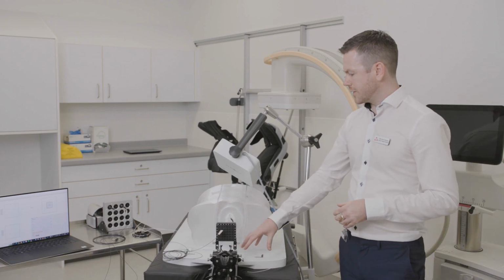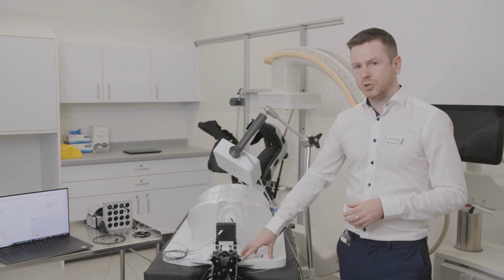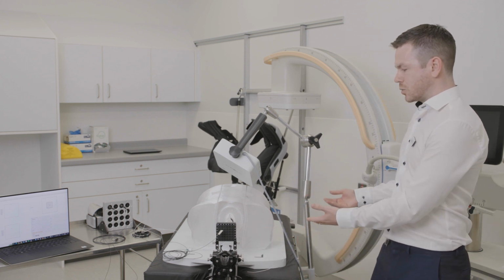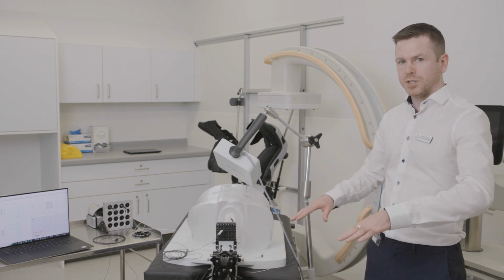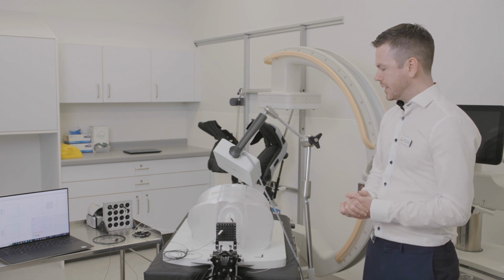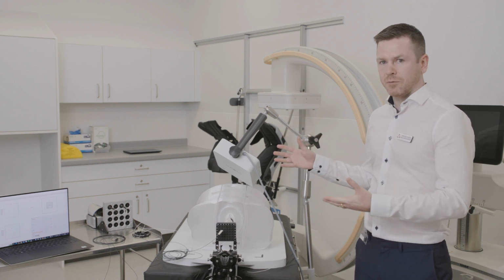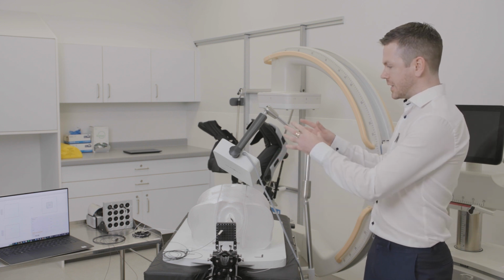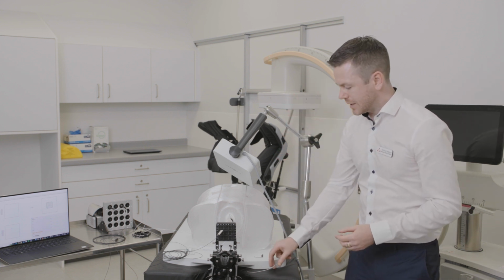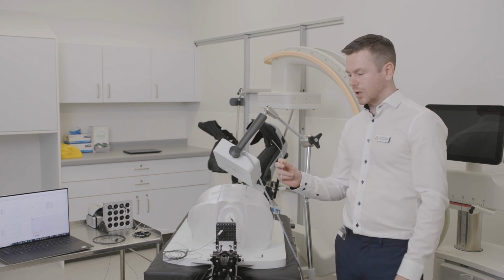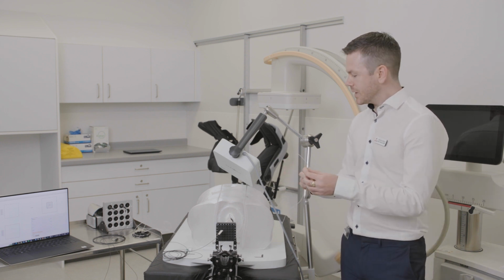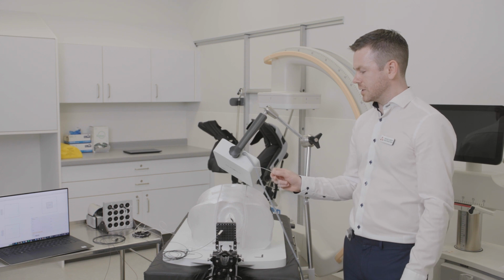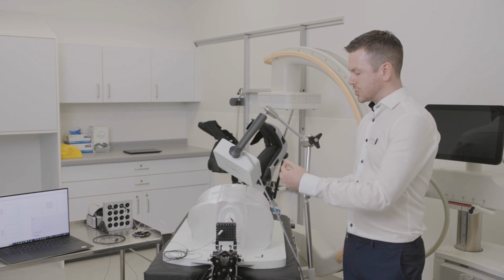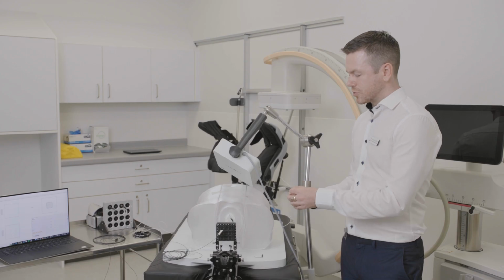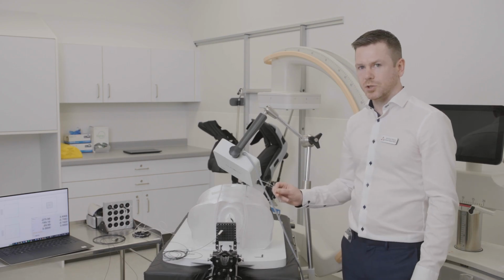Also shown here on the patient couch, we have the tabletop generator. And as the name suggests, this one will be positioned underneath the patient, directly on top of the treatment couch. But the concept is the same for both of these field generators. They generate an electromagnetic field, and then we can use our electromagnetic sensor, which when positioned in the field will allow us to determine its precise location in three-dimensional space. And this works through the process of mutual induction.